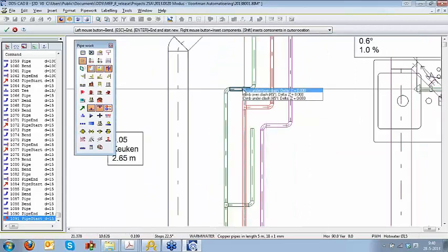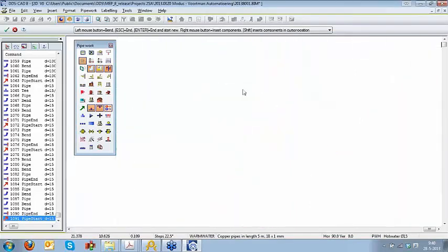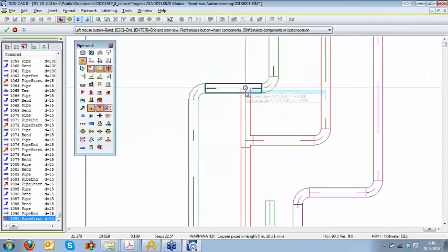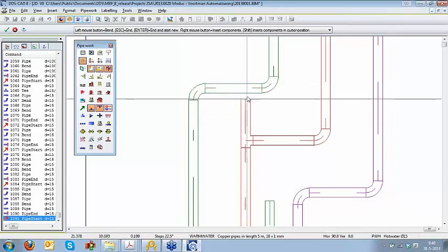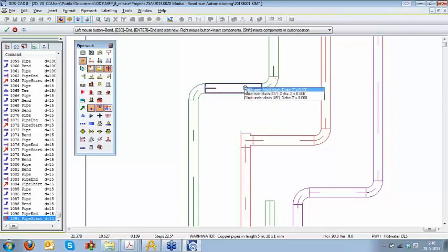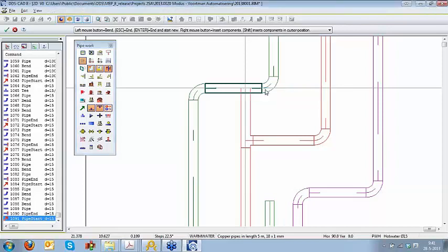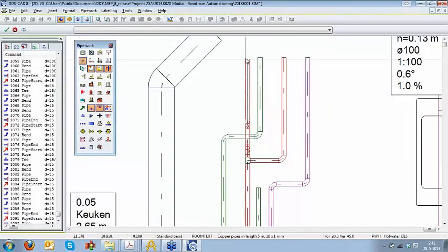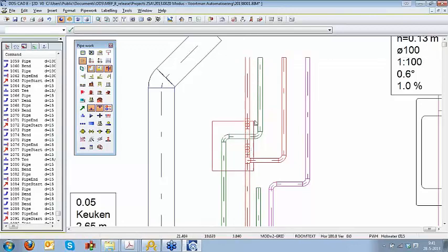And when selecting such an element, we just saw before that we could connect a sewer pipe to another sewer pipe, but it is impossible to connect a hot water pipe to a cold water pipe. So DDS will recognize there is interference on the same height, there is no offset, no delta, and DDS proposed to have a clash avoiding by using a step over this pipe element or a step under this pipe element with an automatic function. So when I go underneath this pipe, we can continue on the other side, and the result is quite nice.